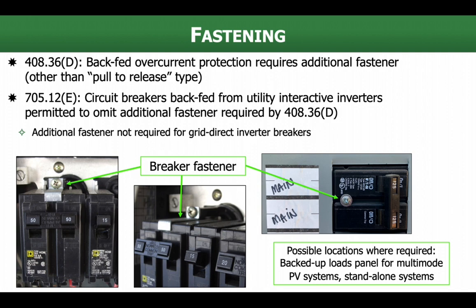Now, there are some instances where if I'm backfeeding a breaker from a PV system, I may need to have fastening. A backup loads panel from a multi-mode inverter, which is made to continue operating the backed-up loads when the primary power source goes away. So it has a connection to the grid. It has a connection to a backed-up loads panel. That backed-up loads panel is going to remain energized from the inverter when the grid goes down. So it's kind of like the generator example. Now that breaker that I'm backfeeding is energized.